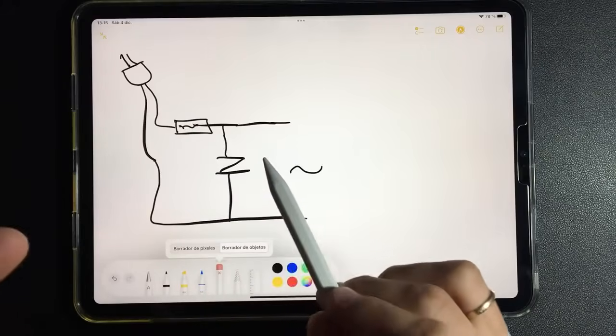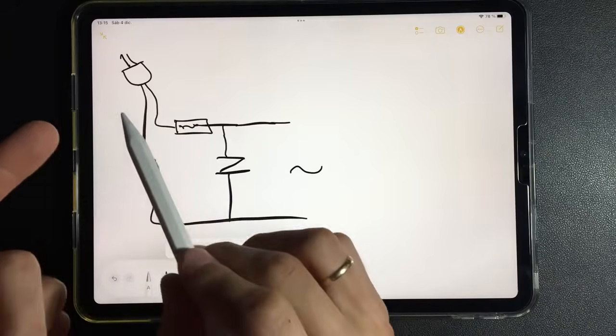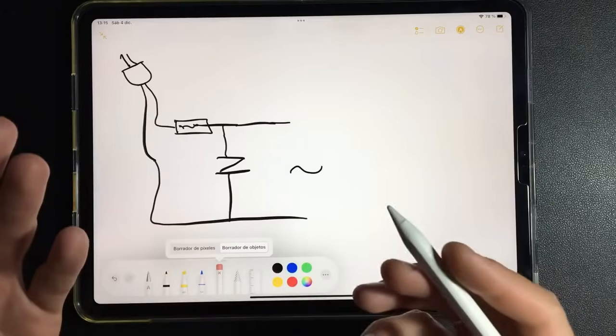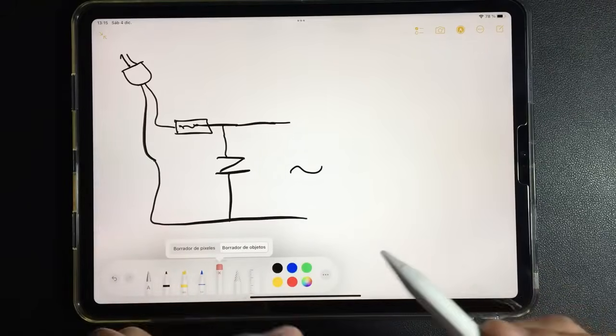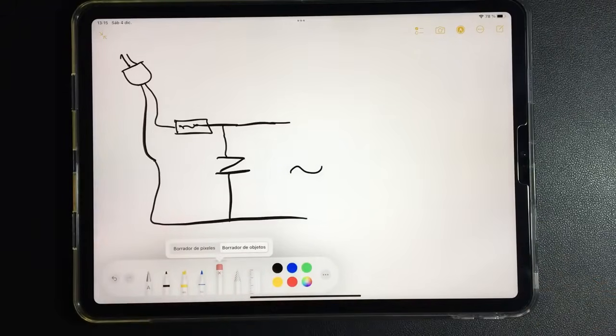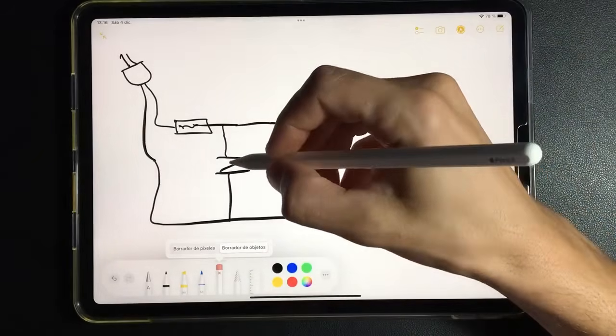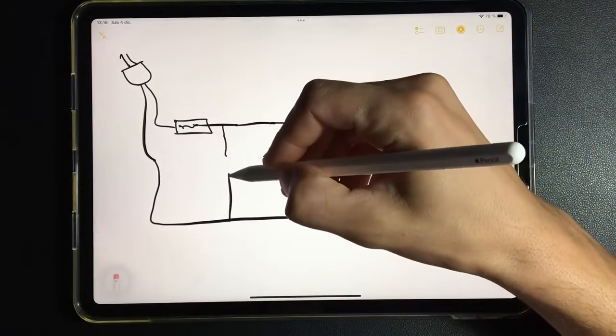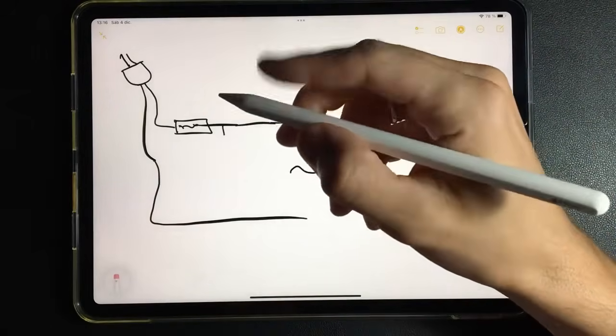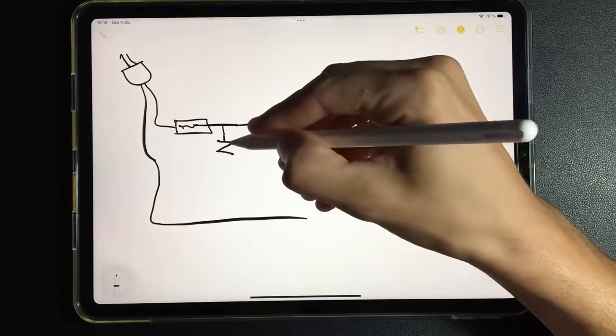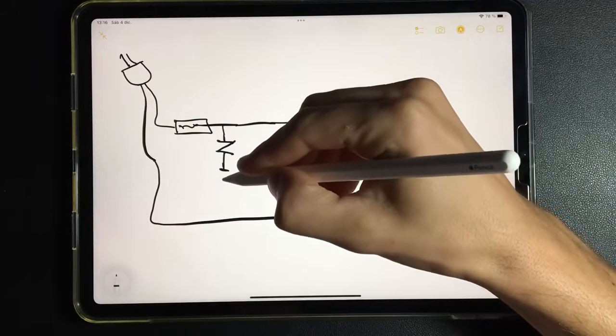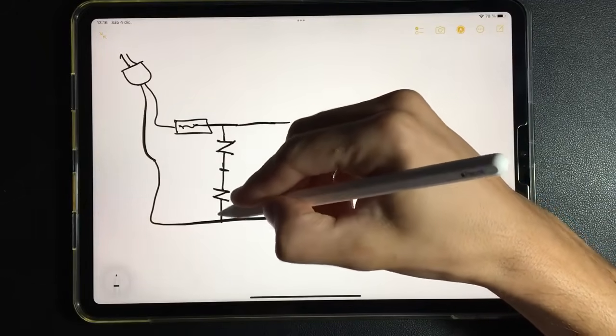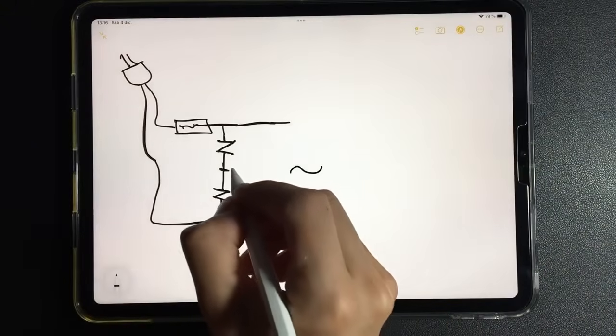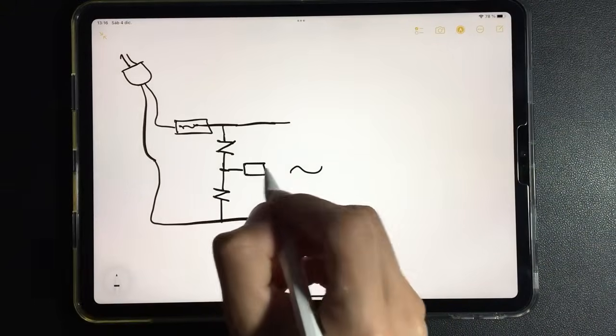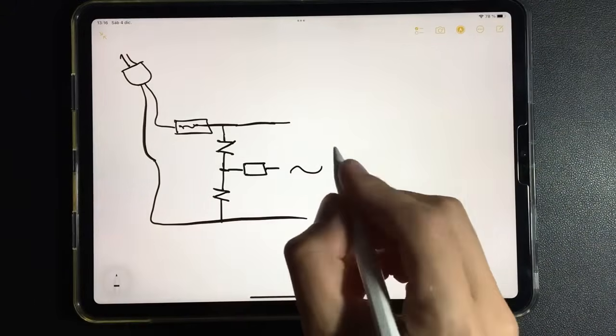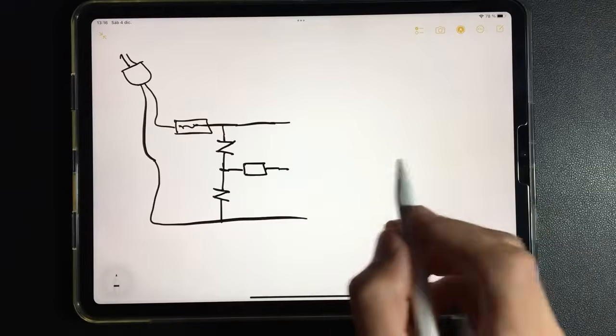Instead it tries to divert this power whenever there is excess high voltage, diverting it to the ground wire so that the circuit breaker trips. So what you will find is not a single varistor joining the two lines, but a varistor here, and here another varistor, then a fuse, and here is where we go to the ground wire.